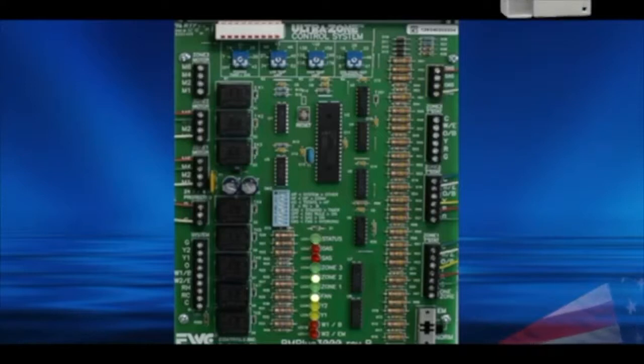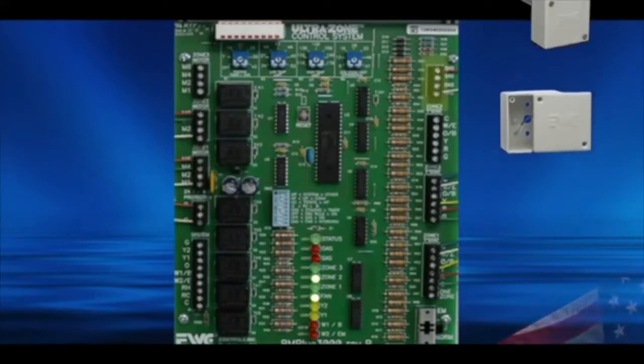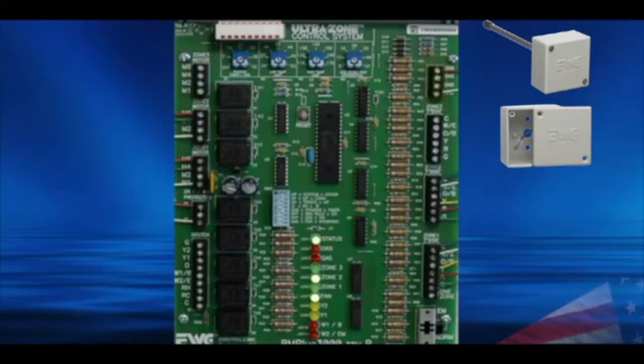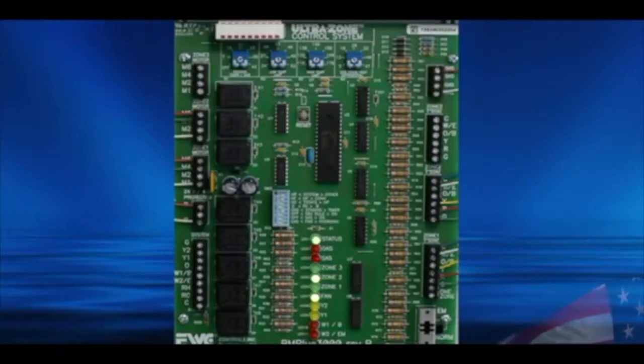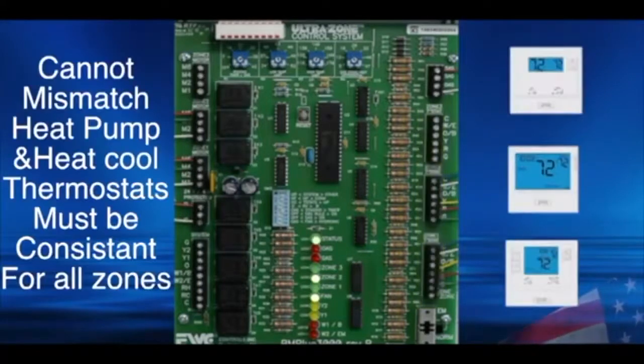Sensor wiring is straightforward. 2 wires are connected to the appropriate sensor terminals. Polarity is not important. If the sensor is not wired properly or shorted, the SAS LED or OAS LED will blink to let you know that the sensor needs attention. Thermostat wiring is also made simple. Just wire your straight cool or heat pump thermostat through the appropriate zone, 1, 2, or 3 terminal block, and that thermostat will control the corresponding damper for that zone.